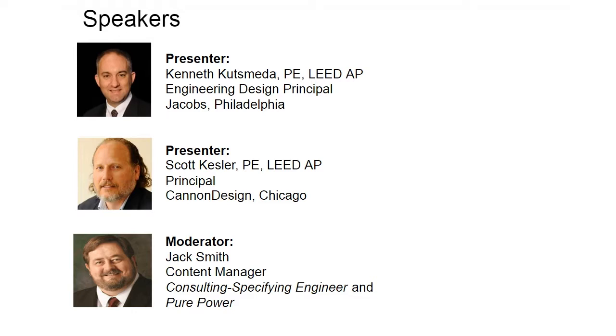Sure, good question. There's really two parts to that. The lighting that's in the elevator cab is required to be on the life safety branch. The elevator motor itself is on an equipment branch. Typically what I'll do, because you'll have a bank of elevators, and oftentimes given how the distribution system works out, it makes a lot of sense to have all of the elevators in that bank or in the facility on a separate transfer switch, separate from other equipment loads. It just helps to allow for easier control in the load shedding sequencing that we talked about earlier.